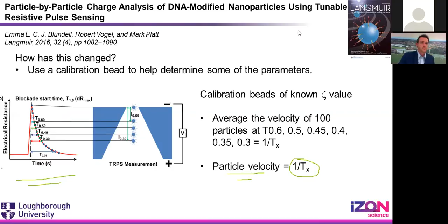So by not doing an individual measurement, and instead taking multiple measurements across that pulse, you get a better average, and it allows you to be a bit more reproducible in the measurements. So I plot the durations, I measure the pulse widths at different locations, and 1 over this average velocity gives me my particle velocity. It's a way of determining how fast the particle is going through the pore. So the concept is very simple. If I have my sample and I measure its velocity, it's going to be related to the calibration's velocity by this equation. Let me get my annotation tool back up again. This relationship between my sample zeta potential and my calibration zeta potential can be worked out simply by saying that if the velocity of my sample is the same as the velocity of my calibration particle under the same set of conditions, then the zeta potentials must be equivalent.